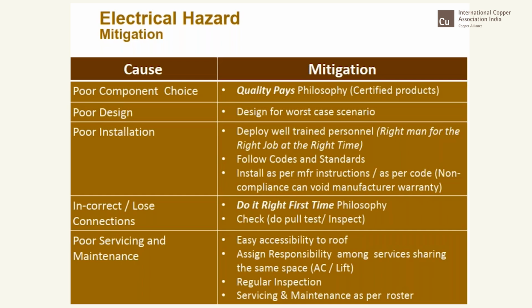Then again, incorrect and loose connections, this is very, very common, and this is where we also don't exercise care. And of course, poor servicing and maintenance, which need not be overemphasized. As I was telling you earlier, there has to be easy accessibility to the roof, and we have to assign responsibility, especially when the same services are shared. For example, on the roof there could be an AC technician coming, a lift operator coming, or somebody going to the tank to wash it, because everything is not off.